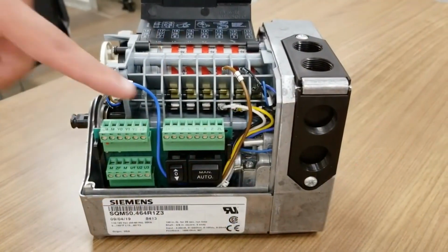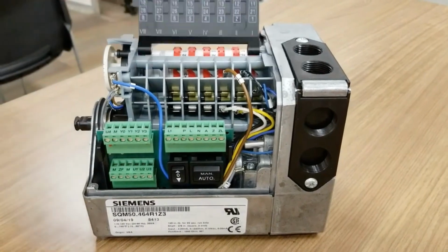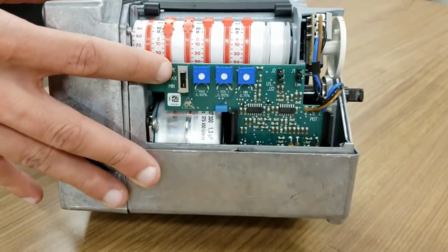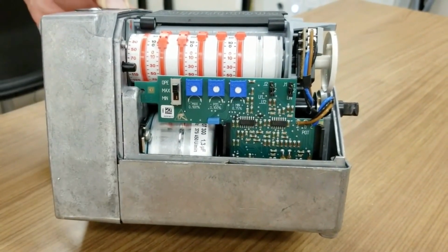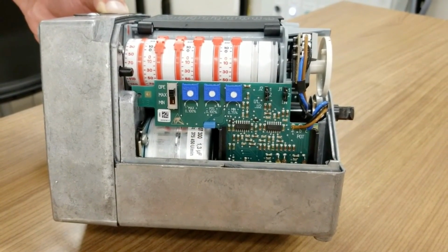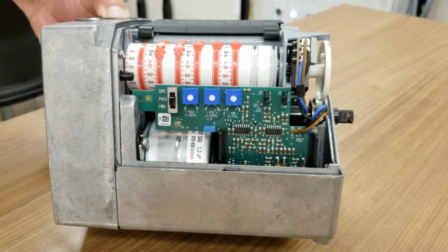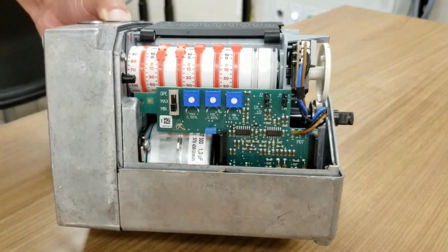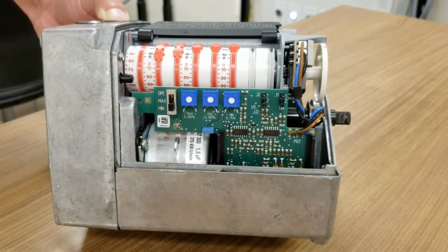While the motor has the L1 terminal powered and you're set to modulate, this OPE min-max switch on the back here also has some functionality. If it's in the OPE position, that means that the motor will modulate based on whatever input signal is being given to the motor. If you flip this to the max setting, it'll drive the motor up to cam position 1. If you set this to the min setting, it'll drive the actuator down to cam position 3.